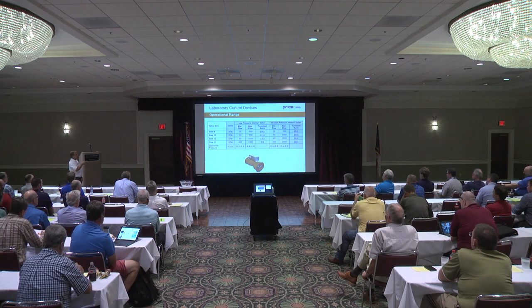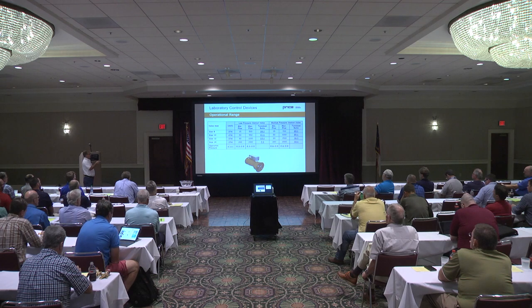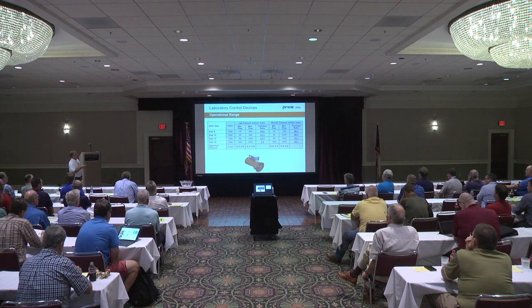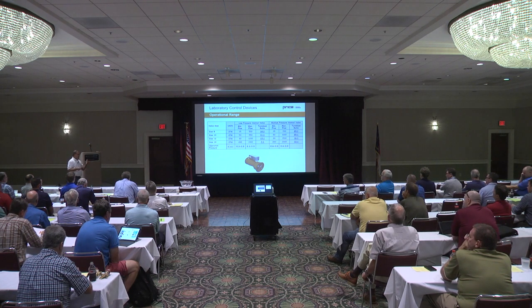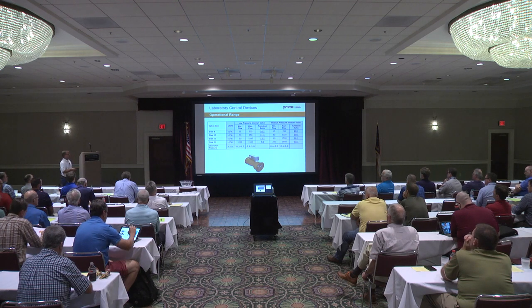But if you look at the maximum flow range, the low pressure valves get derated to be able to deliver the airflow at the lower differential pressure. You lose a little turn down because your maximum flow has been reduced. But you can see a significantly higher turn down on the Venturi valve. And this becomes important in laboratories where we've got fume hoods, where we have to adjust the supplies and general exhaust based on fume hood demand. So turn downs become very important inside a lab control.